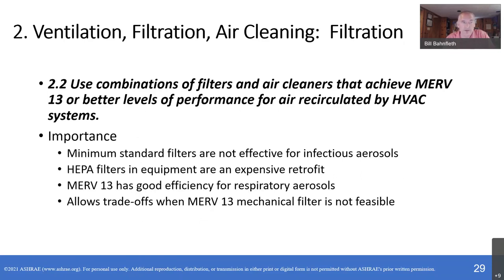This addresses filters. And initially, we said rather bluntly, use MERV 13 filters for recirculating airstreams. And this has been modified to a statement that combinations of filters and air cleaners that achieve that level of performance are acceptable. So that could mean using multiple filters in series that aren't MERV 13, or using a lower MERV filter with some kind of air cleaner.